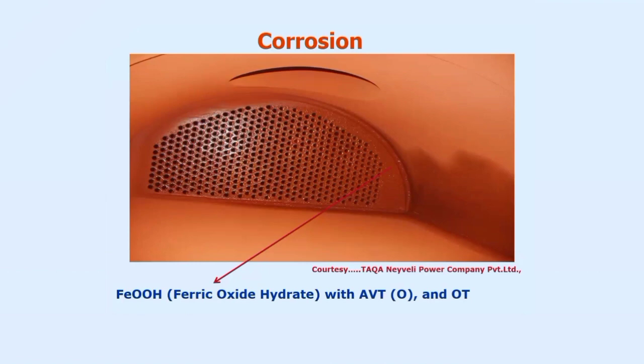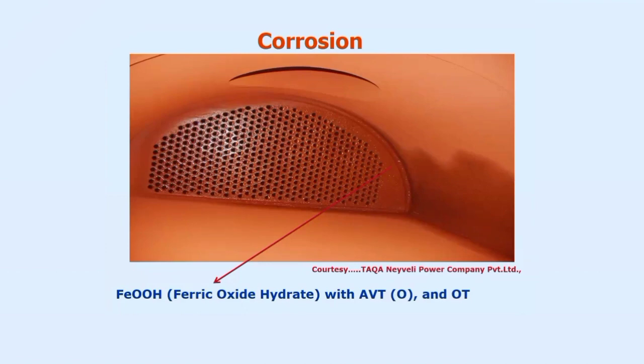This hematite protection is developed when we are using either AVT(O) or OT treatment. AVT(O) stands for all-volatile treatment oxidizing, and OT stands for oxygenation treatment. In most of the supercritical systems, they are either working with AVT(O) or gradually going to OT treatment.